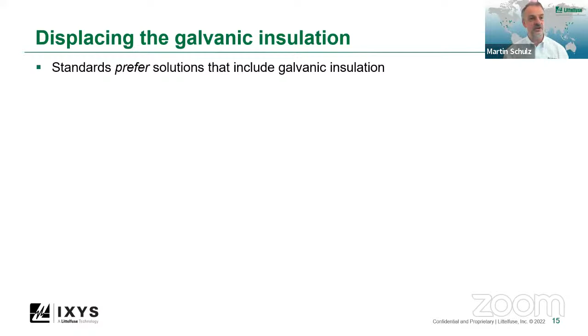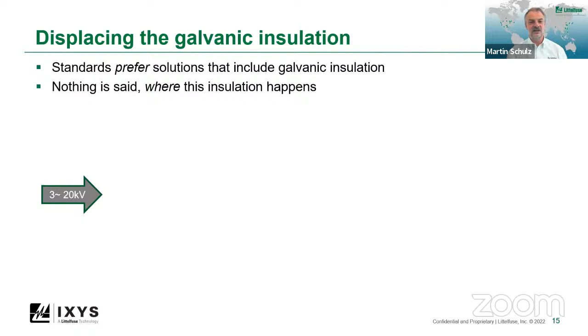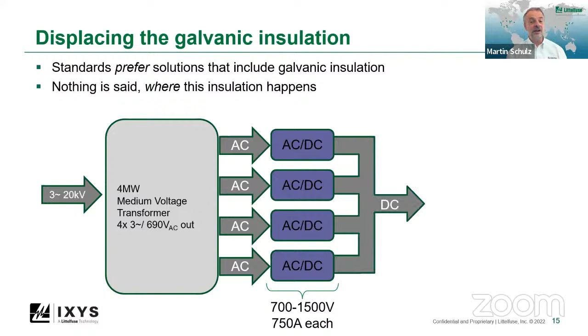If we're talking about megawatts, we're not talking about taking it from the low voltage 400 volt systems. We're talking about a massive backbone connected to the medium voltage regime, 20 or 30 kilovolts. So a megawatt transformer can be created to produce several outputs of 690 volts, for example, and each of those outputs can drive an AC to DC converter. Well aligned, each of those could provide something like the 1500 volts targeted for high power vehicle charging. And if each of those provides 750 amps, four of them would easily provide the 3 kiloamps that the standard mentions. Paralleling those for the DC may easily provide the megawatts to a single vehicle.